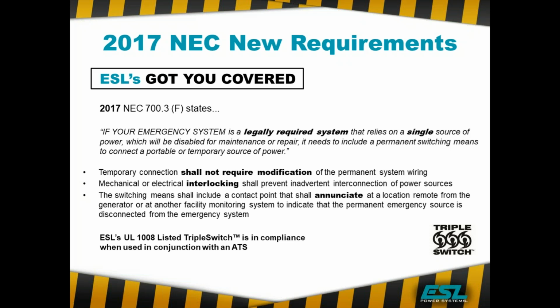Okay, keep in mind that a lot of the authorities having jurisdiction are expanding on this requirement in the sense that a lot of them will come back to the designers or the owners and ask if a building is going to be occupied by people. If there are a lot of people in this building, we see this more and more with certain office buildings. They'll require that building meet the 700.3(F) part of the code, even though they may not be a legally required building at the time. Because it's occupied and it's got a permanent generator, they'll require that the design include some sort of backup. So just a heads up on that.